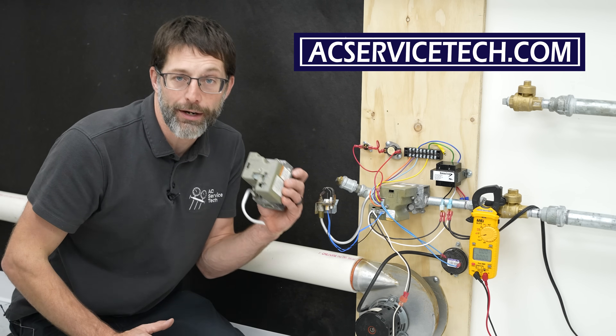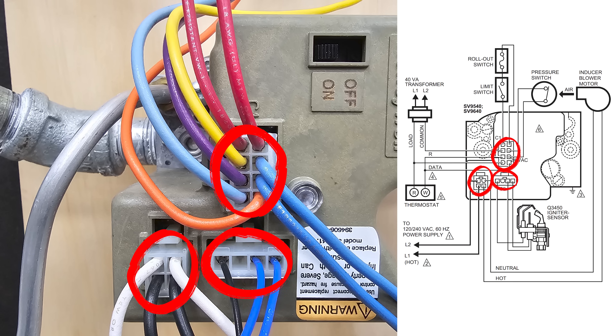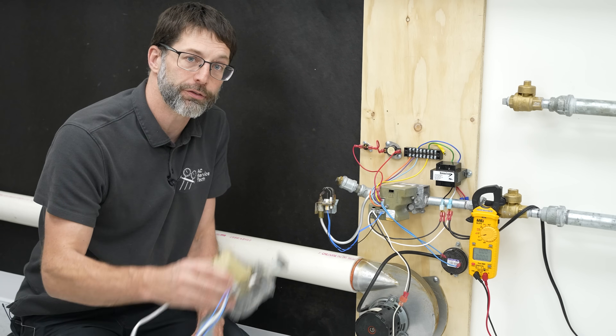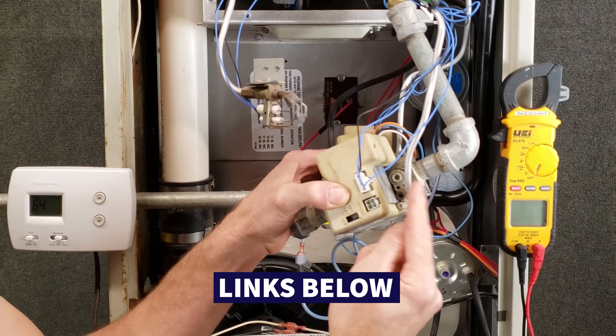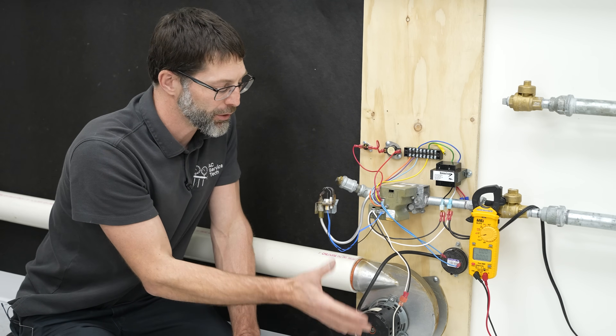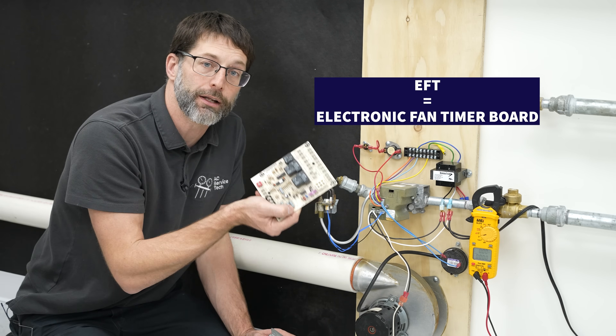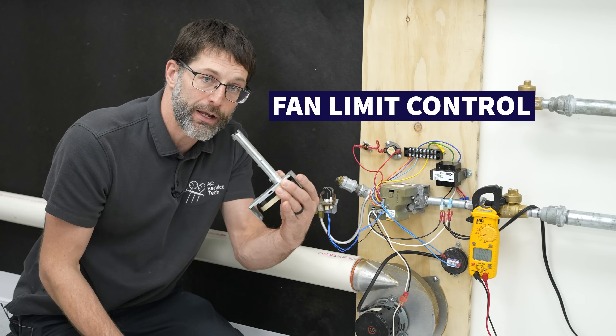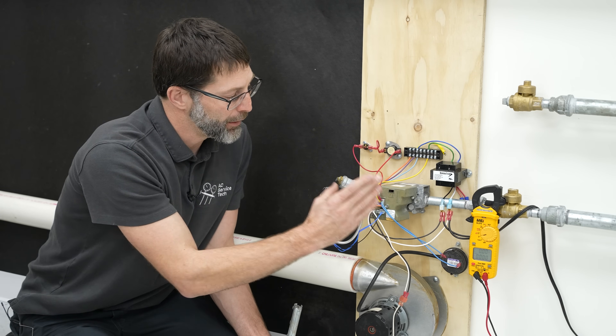This is Craig Migliaccio from AC Service Tech and today we're going over a Honeywell smart valve operation. This style has three wiring harnesses and requires both 120 volts and 24 volts to operate, and this one is a pilot ignition valve. We've done several videos on the style that only requires two wiring harnesses and 24 volts to operate — that's linked in the description below. This smart valve controls the entire combustion and safety aspect of the gas furnace.